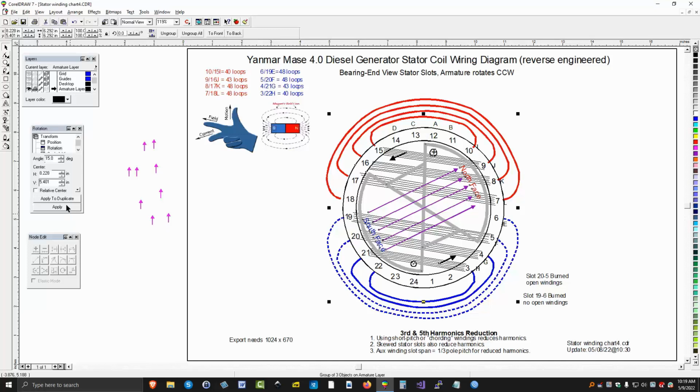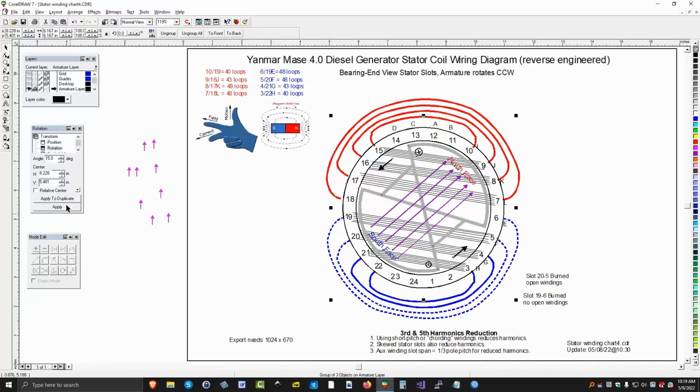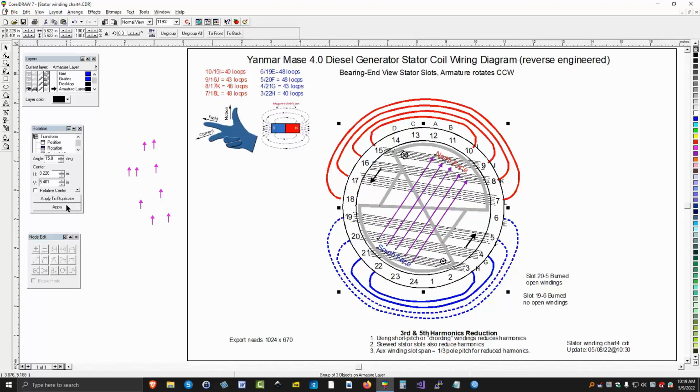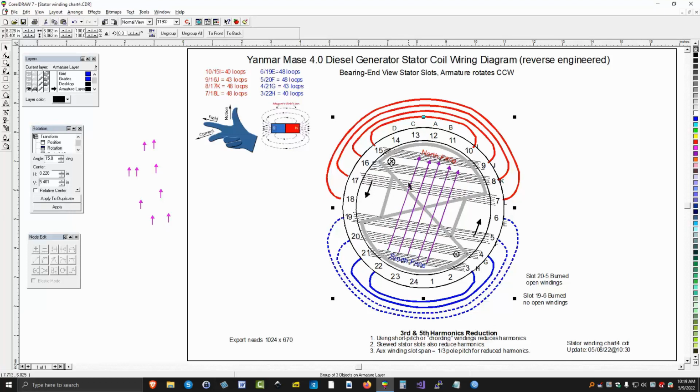And we keep rotating, we keep dropping the current until something peculiar happens. Still dropping the current. But now look what's going to happen on the next step. On the next step, we shorted out 15 and 10. In other words, this north face is trying to put current into 15, and it's also trying to put current into 10, so they cancel, so you get no current. So that cuts that current flow off from that winding. That winding drops out as far as current flow is concerned.